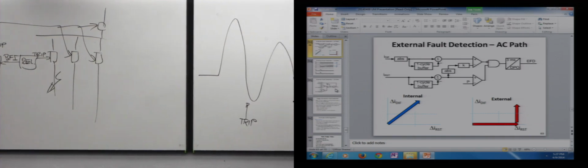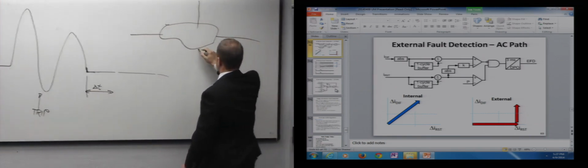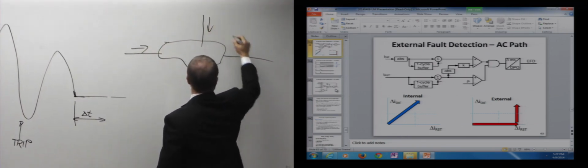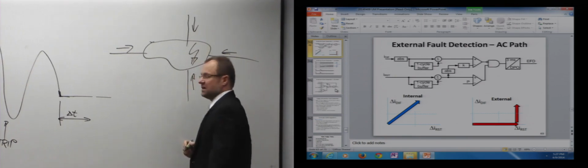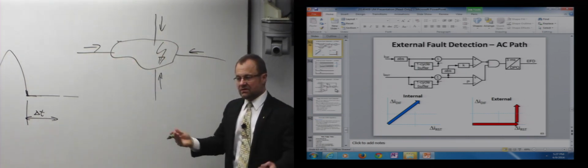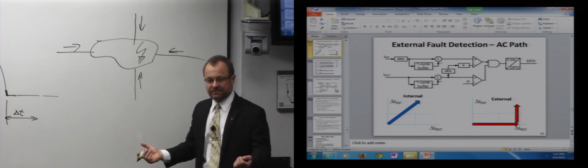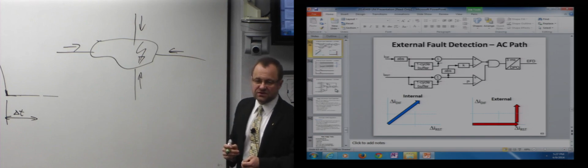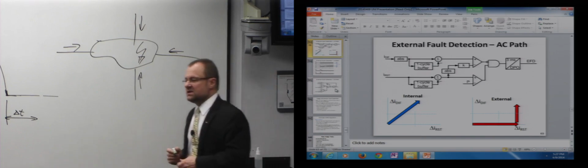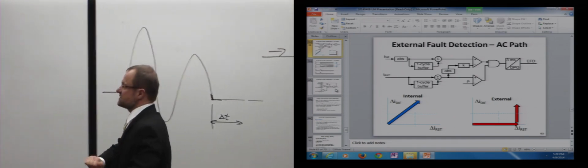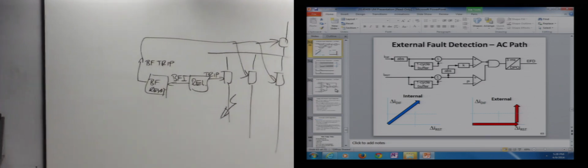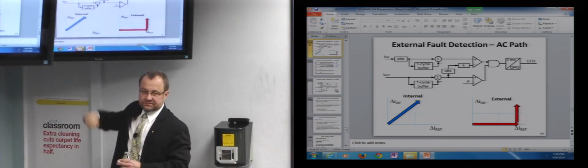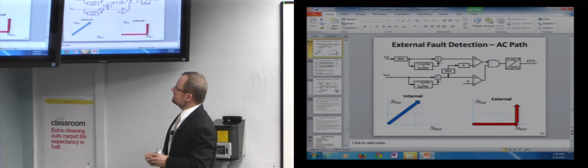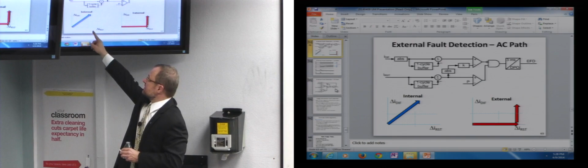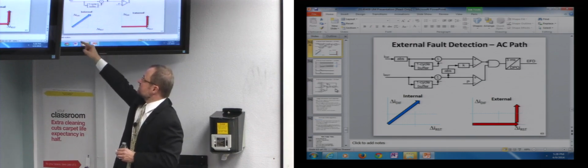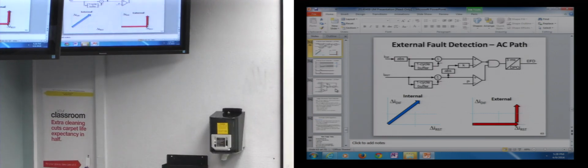So what happens if you have an internal fault? Let's assume that this is our protected element, whatever it is, transformer, bus, or line, and you have a couple of currents that you measure, and you have an internal fault. There are sources everywhere, and all those currents respond to a fault. What happens to them? They go up. What happens to the differential current? It goes up, right? So if you monitor the changes in the differential and restraining current, this is what you will see. This kind of trajectory. I was sitting at 0 because that's pre-fault. A fault happened, and the feeds that feed the current inside the zone went up, and the differential current went up, right?